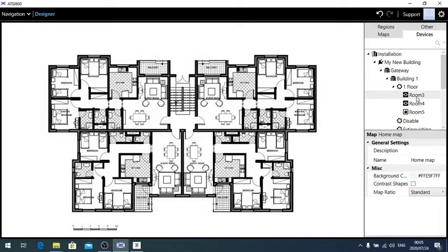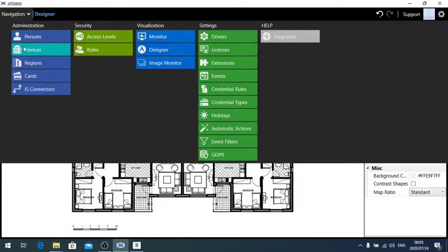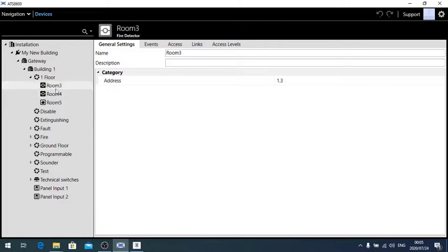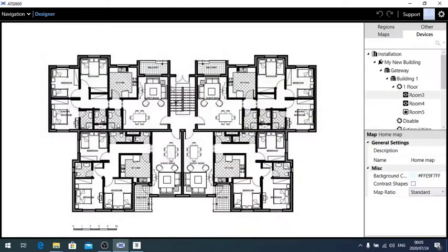But the guy who gave me the as-built showed me device 1001 or 1002, which is the detector number. I can't see it here. So now it starts getting a guessing game, or I need to go back to devices and find this is 1003 and I need to go back to design.